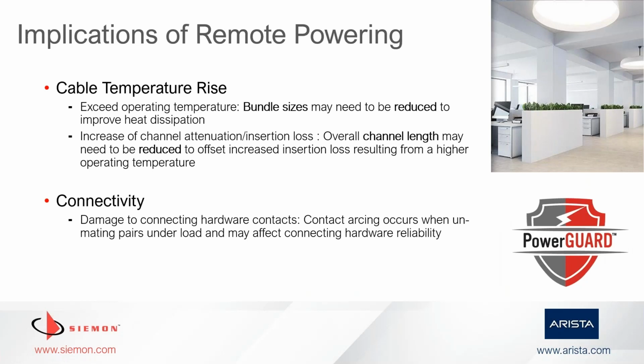So in this sense, the implication of remote powering on the cable structure would be mainly coming from a potential temperature rise. The first effect is power loss. That means cable heating increases the insertion loss, and this might mean exceeding the operating temperature. We can mitigate this with the right installation practices, and the overall channel might need to be reduced in some cases if you don't take good care of the design in cable to offset the increased insertion loss.